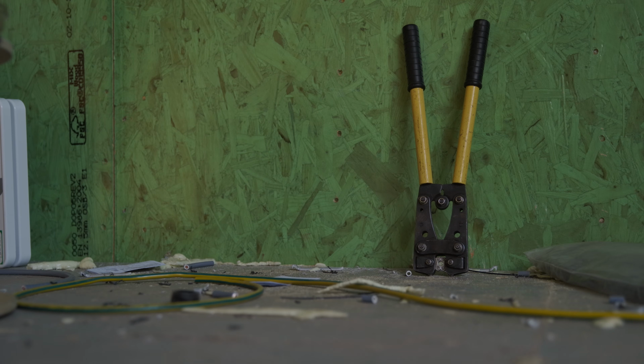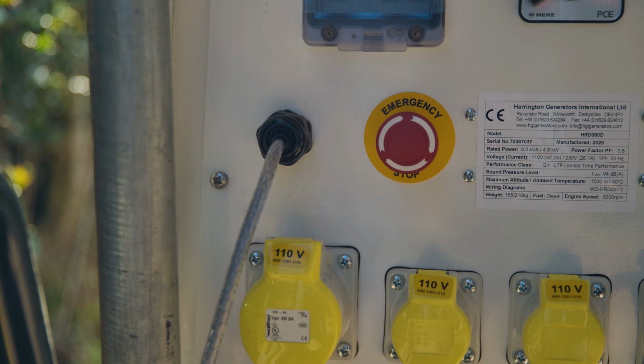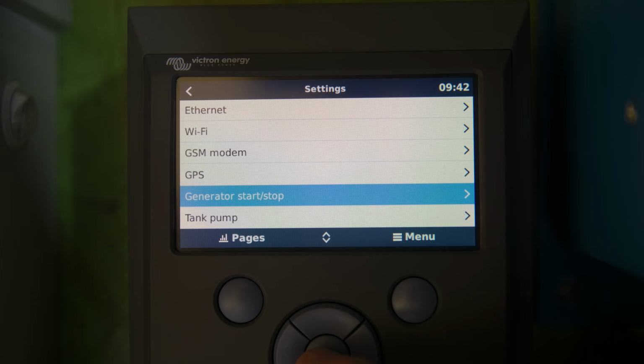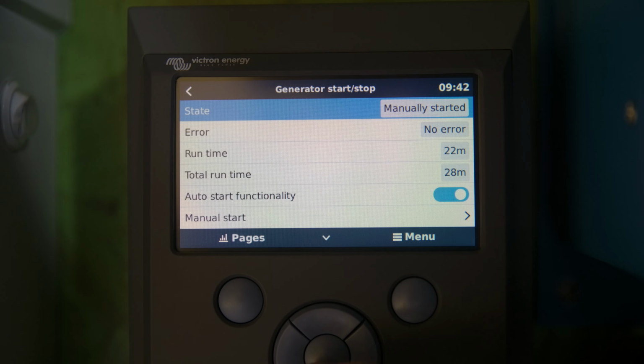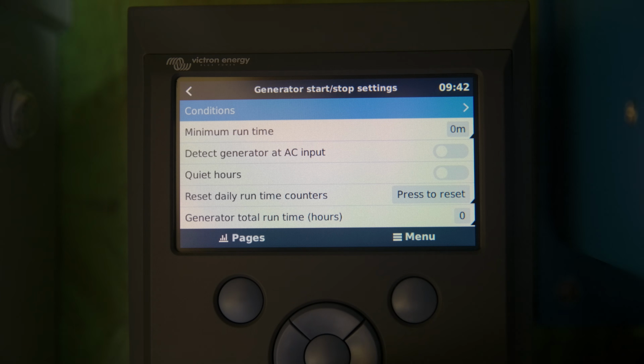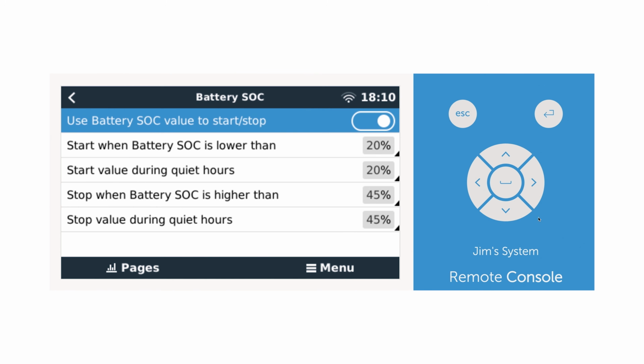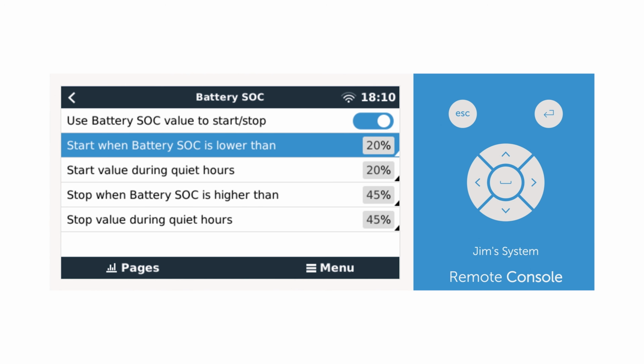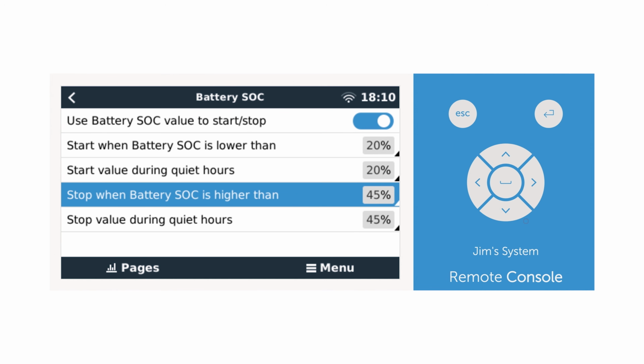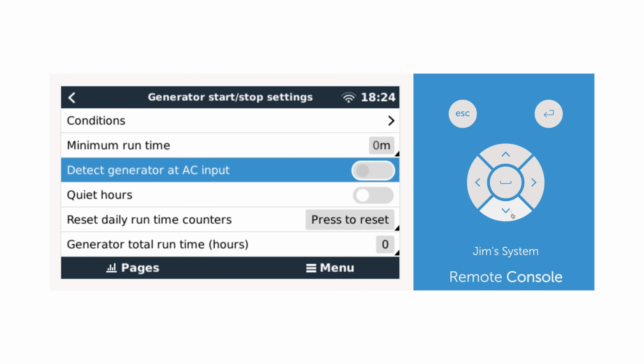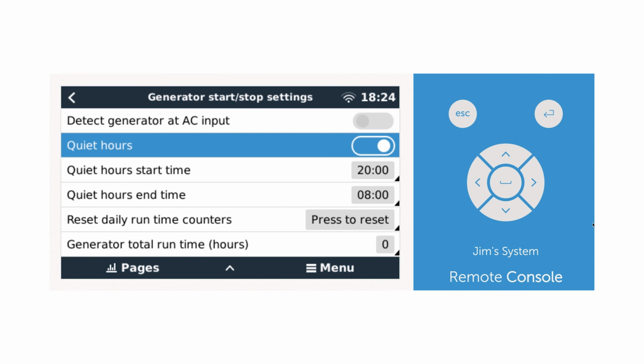This generator can be automatically started, so an armoured communication cable is wired up to the relay within the Victron Colour Control GX. Currently 2 presets have been set up within the Colour Control GX. If the battery state of charge is lower than 20%, the generator will be automatically turned on and run until the state of charge reaches 45%. Although automatic, this can be restricted to chosen time periods to avoid noise at night, for example.